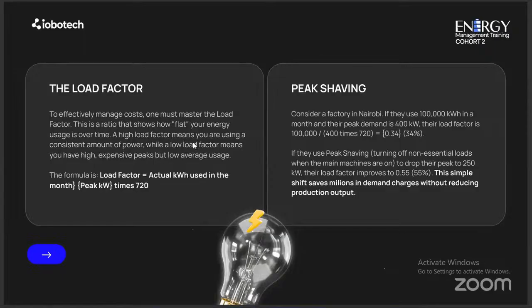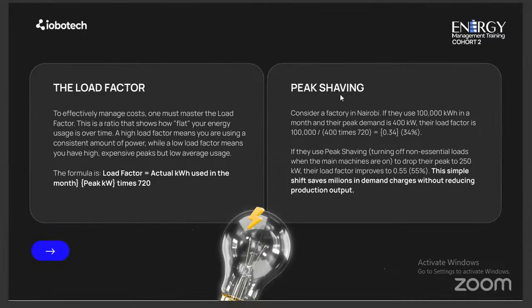So for peak shaving, consider a factory in Nairobi. If they use 100,000 kilowatt hours in a month and their peak demand is 400 kilowatts, their load factor is 100,000 divided by 400 times 720, which equals 0.34, which is 34%.